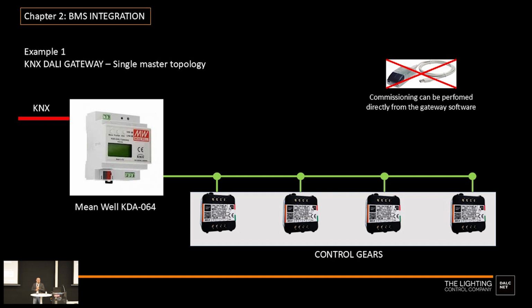Of course, KNX, especially here in Europe, is one of the most diffused BMS system, if we can call it BMS. There's many manufacturers, many different applications, from the small residential to the big industrial application, big buildings, and so we are aware that KNX is a reality that is very strong. The main issue is that, of course, DALI and KNX cannot speak directly, but we always need something that converts the KNX command to a DALI signal. This conversion is done by what is usually called a KNX DALI gateway. And the KNX DALI gateway is quite a complex device because it requires the function on the KNX side, a lot of function on the DALI side, and it requires to do the commissioning.